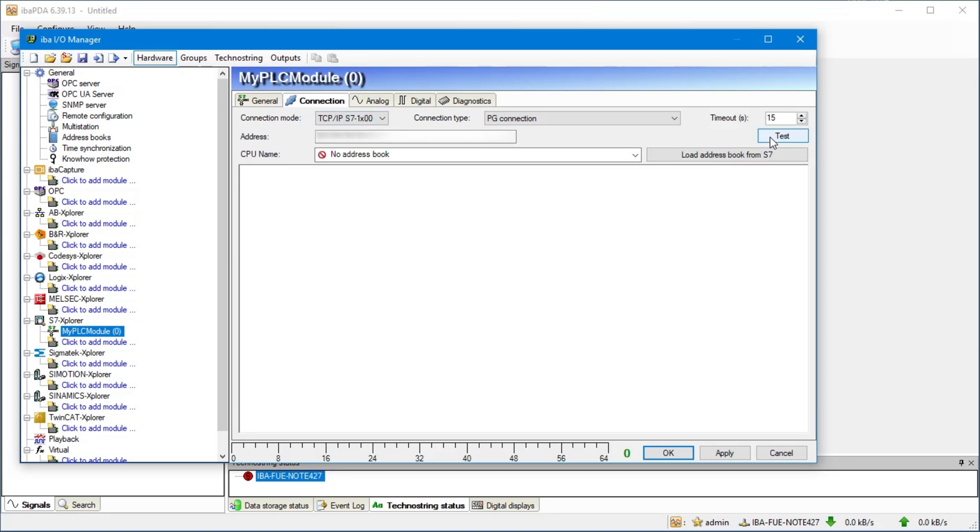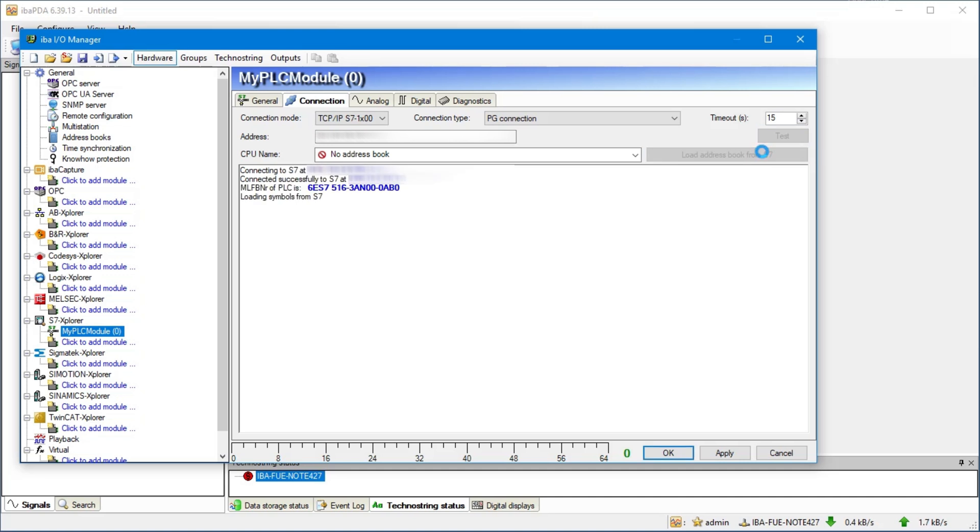Using test we conduct a connection test and get some diagnostic data from the controller. Now we read the address book directly from the PLC by pressing the button load address book from S7. The STEP 7 project files are not necessary for this.